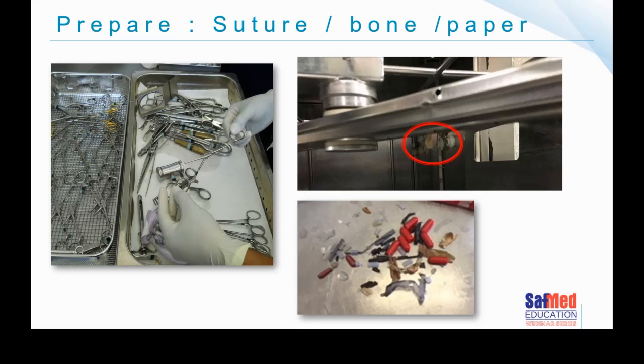The image shown is actually a chemical indicator that somehow slipped through the sieve at the bottom of the chamber and ended up in the spray arm, clogging the nozzle. The items at the bottom of the slide were all taken out of a spray arm one day — it was quite scary how they managed to get in there.